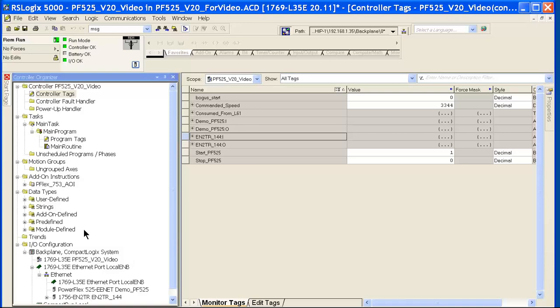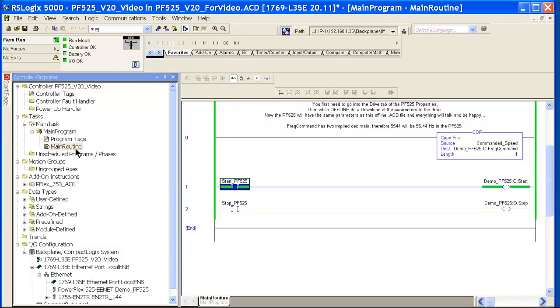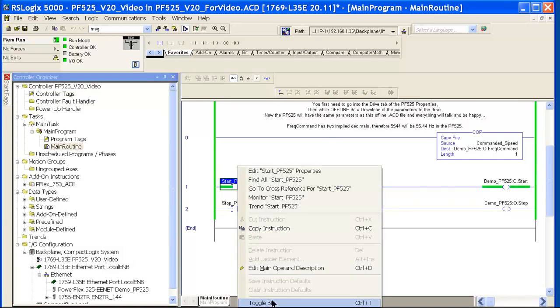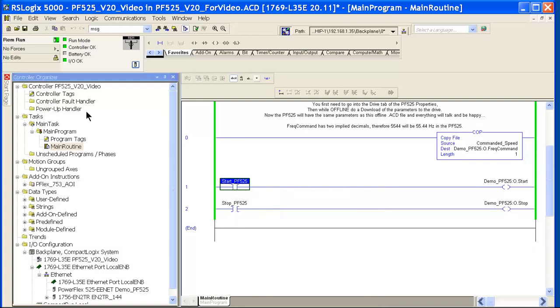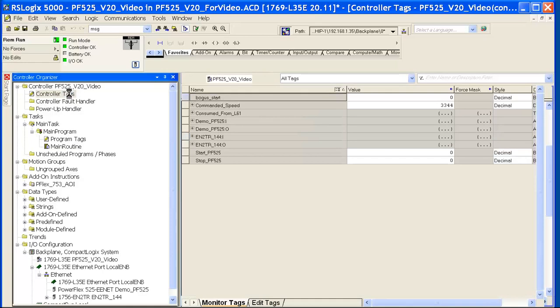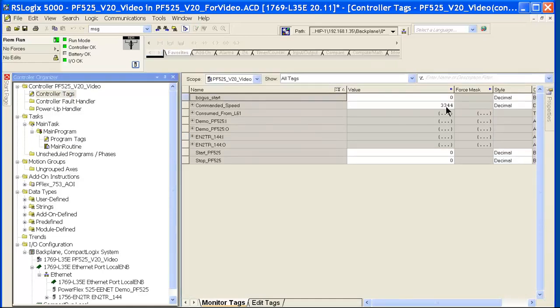That's about it. I did put in just a couple of rungs of logic here to start and stop the drive. I've got a tag called Commanded Frequency. One thing to note, Commanded Frequency has two implied decimals. So if I want to run my drive at 33.44 hertz, I put in a value of 3344.